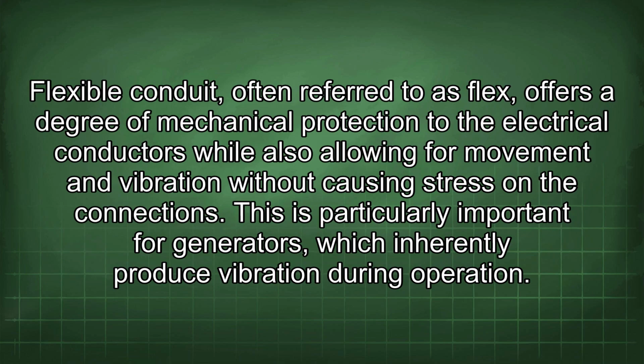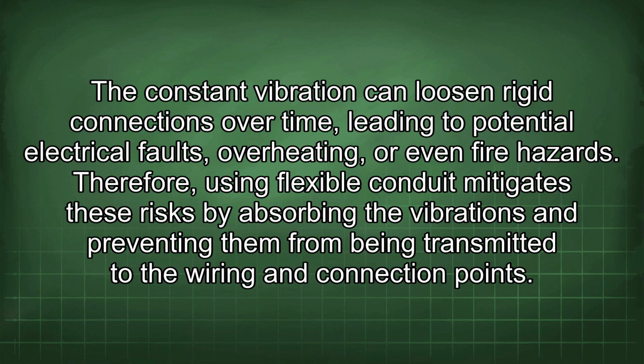Flexible conduit, often referred to as flex, offers a degree of mechanical protection to the electrical conductors while also allowing for movement and vibration without causing stress on the connections. This is particularly important for generators, which inherently produce vibration during operation. The constant vibration can loosen rigid connections over time, leading to potential electrical faults, overheating, or even fire hazards. Therefore, using flexible conduit mitigates these risks by absorbing the vibrations and preventing them from being transmitted to the wiring and connection points.